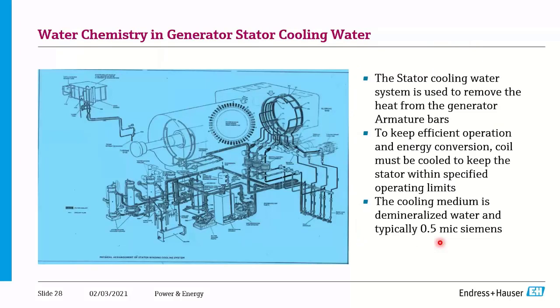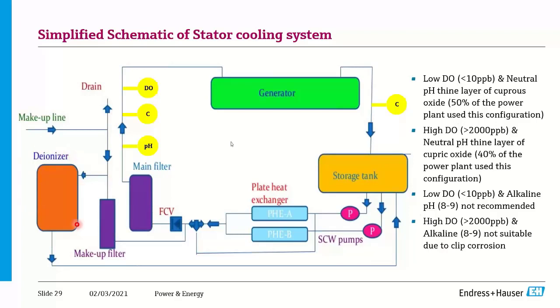An often-forgotten area is water chemistry in generator stator cooling. The generator alternator generates enormous heat, so water must circulate through it — not the surrounding area, but through the stator itself. This package includes a small deionizer pumping water to a storage tank. Before circulating through the generator stator area, it is very important to monitor pH for corrosion prevention, dissolved oxygen — also a corrosion risk — and conductivity to prevent salt formation inside the stator. These are the three basic measurements for generator stator cooling.